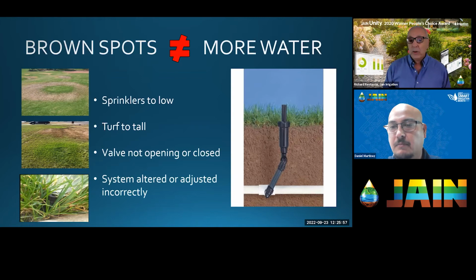That's great, because if you had the rigid riser instead of it just sinking into the ground, that riser would probably break, causing a leak and a bigger problem. But with the swing joint, it just slips down a little and you can pull it back up to grade, compact the soil around it, and you're back in business.